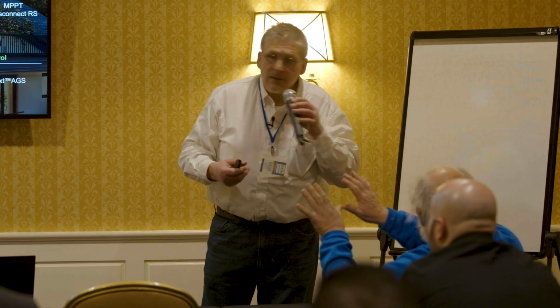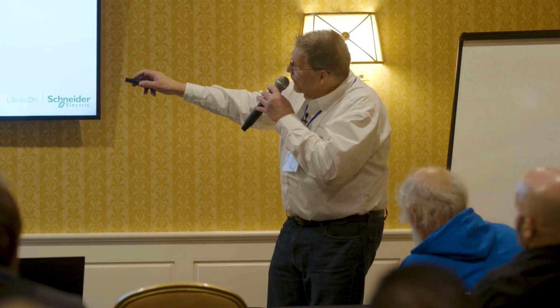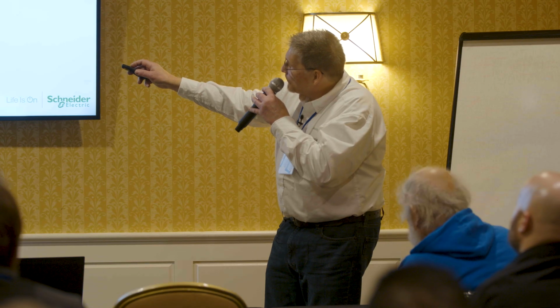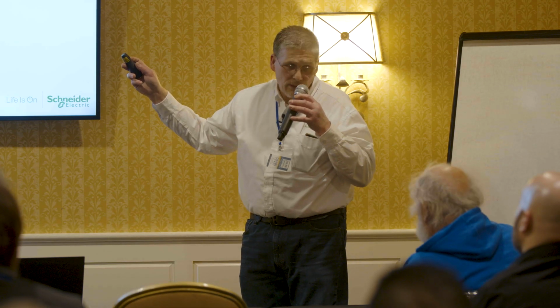You covered it, but I didn't quite understand. How much can I put on a 120 load as opposed to a 240 load? So if you're just running a single line, we can run 4.8 kW continuously at 25C. We can run 6,300 watts for a half hour, 8.8 kW for 5 minutes, and 12 kW for 1 minute. On one line? On one line.